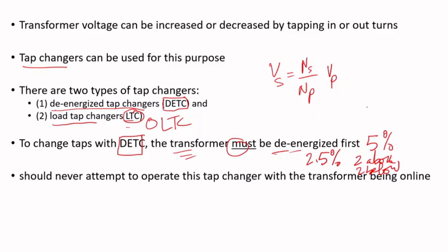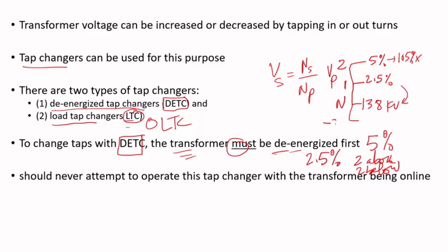For example, with a 138 kV line-to-line voltage as the nominal, if you change one tap up, you go 2.5% above 138 kV. Change it one more time and you go 5% above 138 kV — in other words, 105% of 138 kV. You can also go below nominal, subtracting 2.5% per tap, down to negative 5%.